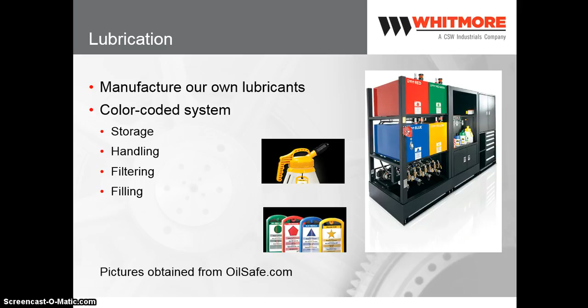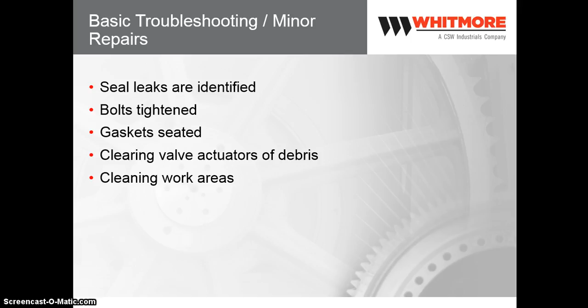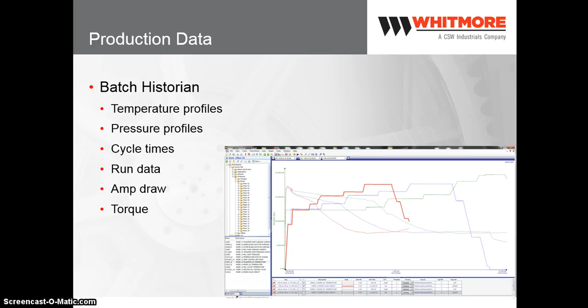So basic troubleshooting, we look for seal leaks, bolts are tightened, gaskets seated, clearing valve actuators of debris in case any of that fine dust gets up in the valve actuators. We don't want to make those stick. And cleaning work areas are also parts of minor repairs and basic troubleshooting. The production data, operators do not need to record any information besides what's on their batch tickets and into our ERP system. Instead, they use the batch historian. The batch historian uses temperature profiles, pressure profiles, cycle times, run data, amp draw, and torque. All that can be tracked and trended throughout any time frame in our facility.